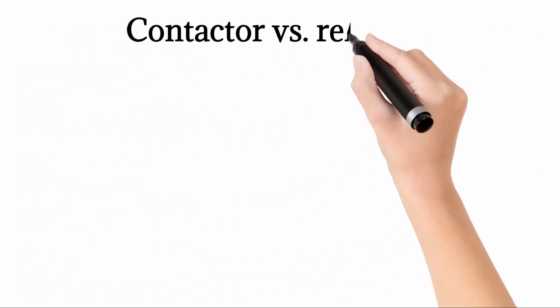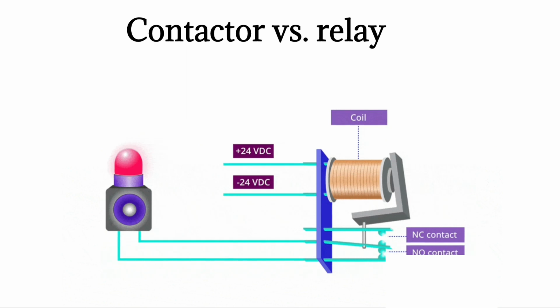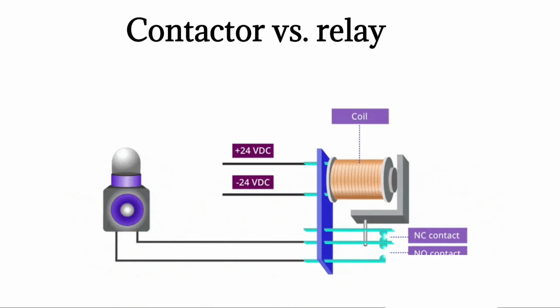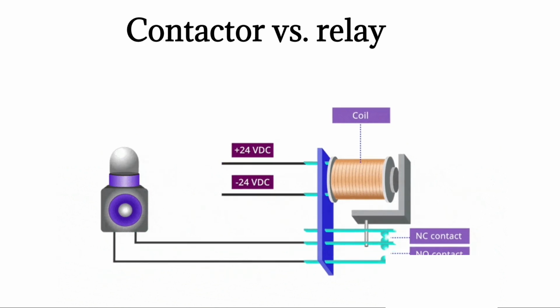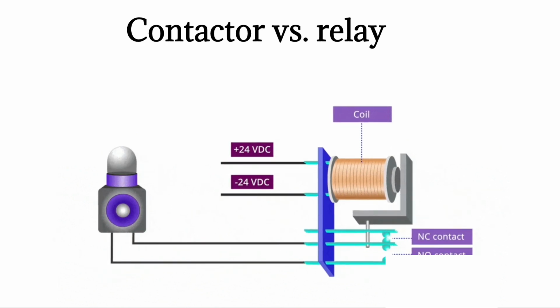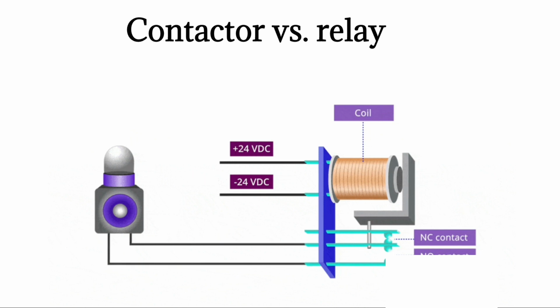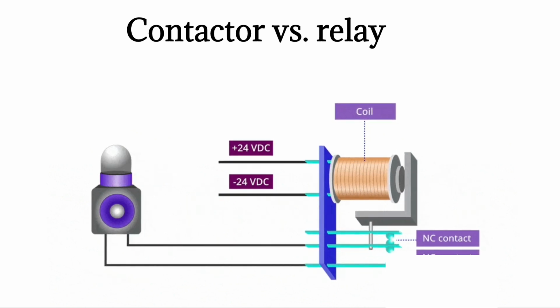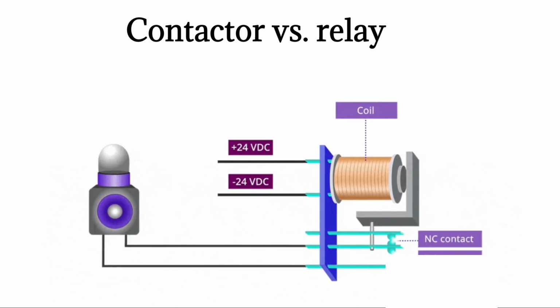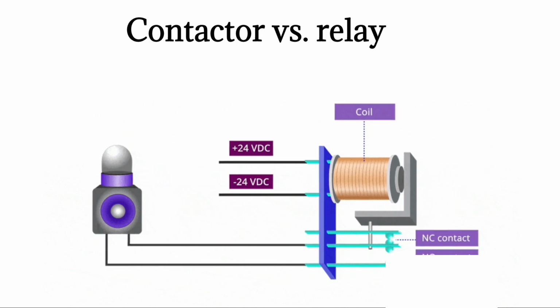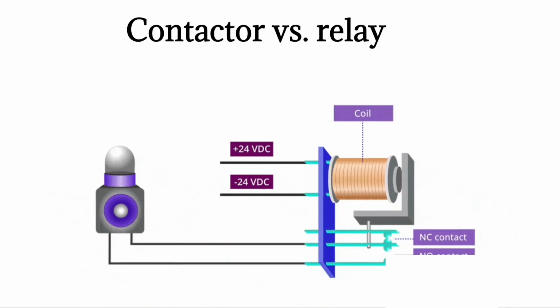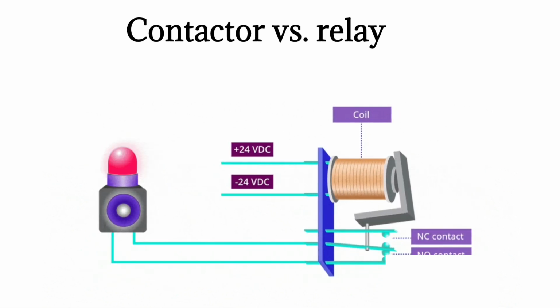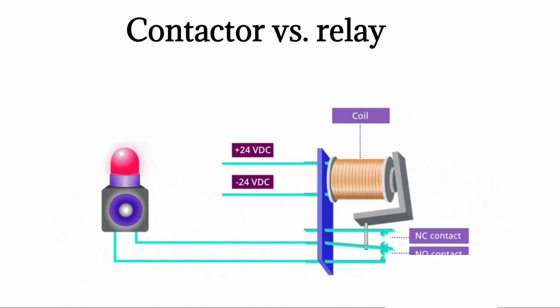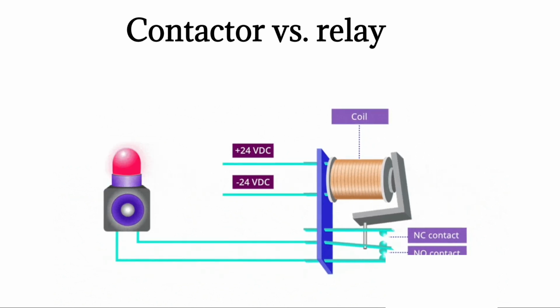Contactor vs relay. Now that you know why we use a contactor, you may want to know how a contactor is different from a relay. You may say, a relay also works in the same way. Can't we use a relay instead of a contactor to turn on the motor here? The answer to this question is no. A relay works the same way as a contactor. That means a relay also has a coil and some contacts. When the coil is energized, the contacts will close. This is the same way a contactor works, right?